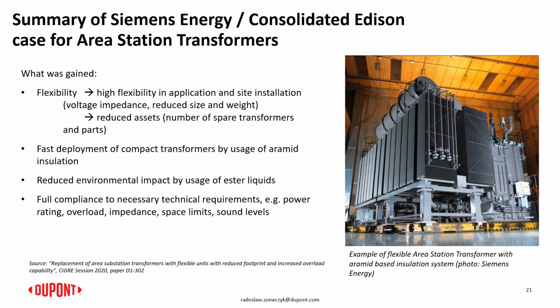So various options for the hybrid insulation of the winding is practiced in those transformers successfully, and more projects are realized with that concept. So this fast deployment of the compact transformers is becoming real, and in case of Consolidated Edison, it becomes a kind of standard solution these days for the specification of the new transformers. Together with the alternative insulation system, when talking about the solid insulation, these transformers use the ester liquids for the fire and environmental protection. So these are kind of state-of-the-art transformers today, and we are proud we can contribute with our materials to those developments in New York.